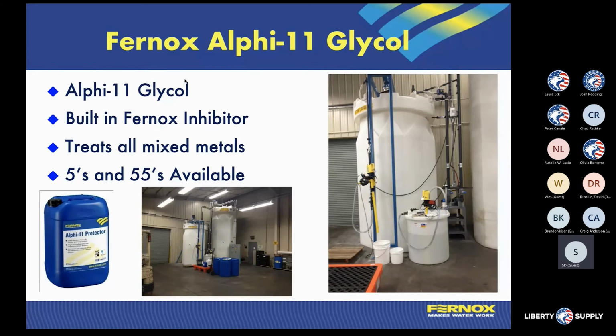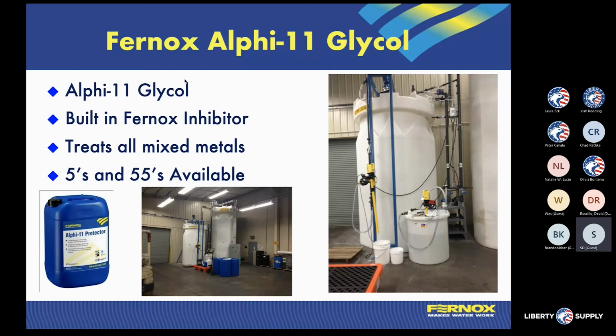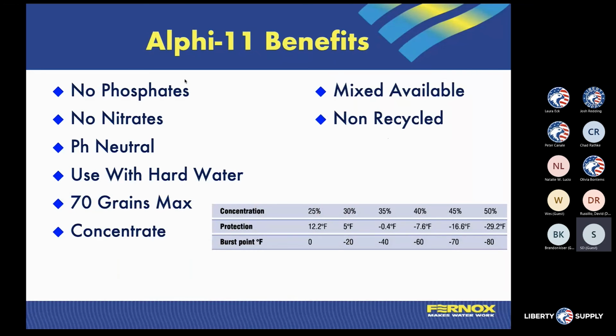Because we've been in the water treatment business for so long, we've seen a lot of systems. We got into the glycol business as well, and we saw a lot of problems with the glycol out there. One is that not all glycols come in a state of neutrality. If you test the glycol you're putting into your system, is it at a 7 or 7.5? We see manufacturers sending out their products at pH levels of 10 and all over the map.